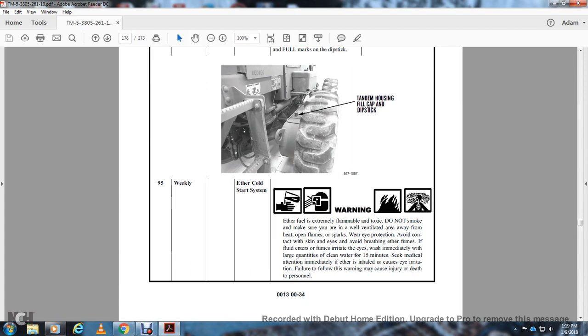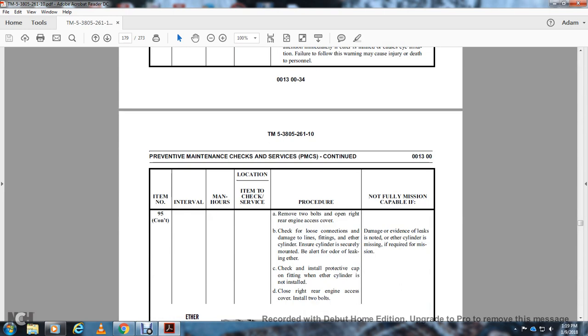All right, item 95, weekly, engine ether cold start. Warning: ether fuel is extremely flammable and toxic. Do not smoke. Make sure the area is well ventilated and away from hot open sparks, and wear eye protection. Avoid contact with the skin and eyes. Avoid breathing ether fumes, which irritate skin and eyes. Flush immediately with large quantities of clean water for 15 minutes and seek medical attention immediately. Ether inhalation can cause irritation. Failure to follow the warnings may cause injury or death of personnel.